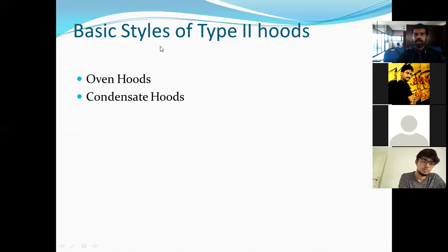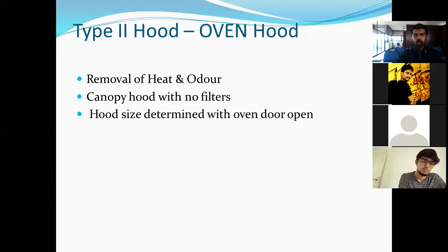Now, type 2 hood, oven hood. Removal of heat and odor. Canopy hood with no filters. Hood size determined with the oven door open. When the oven door is opened, the hood size is determined with the oven's door open, so the size is a little larger. We have to consider that the oven door is open. From that open door only, we will be able to determine the size of the hood.